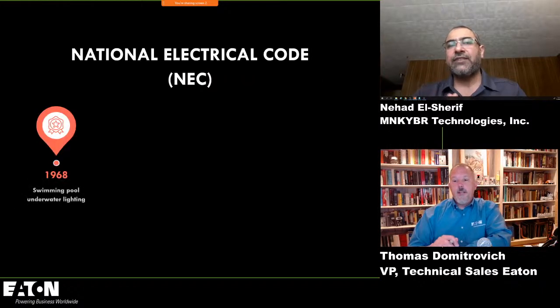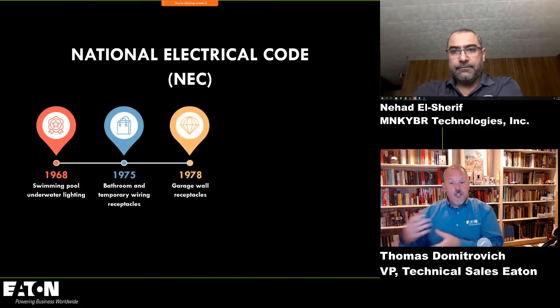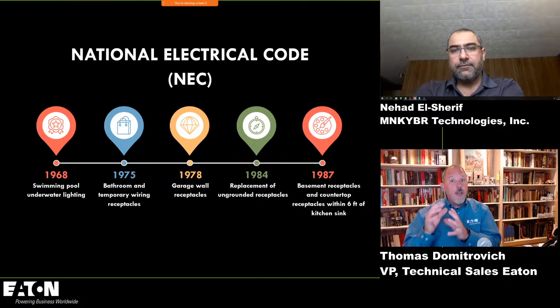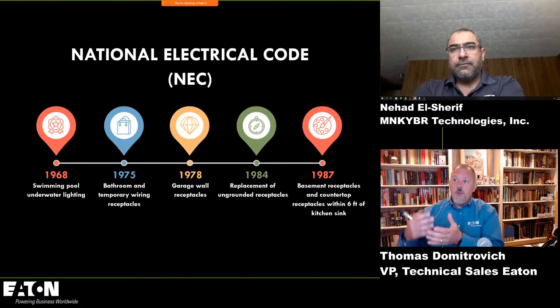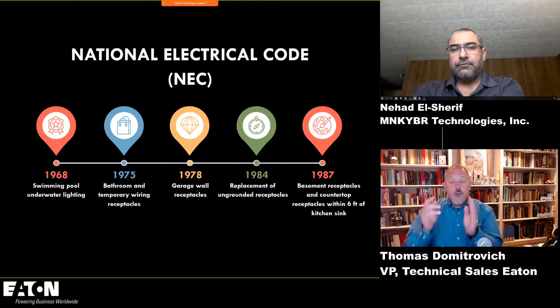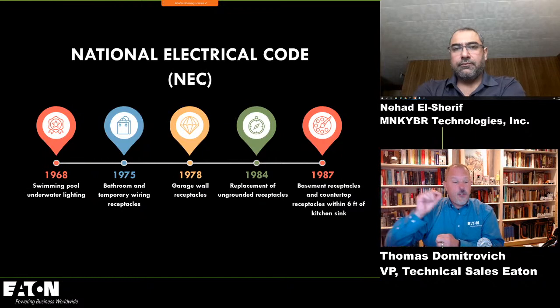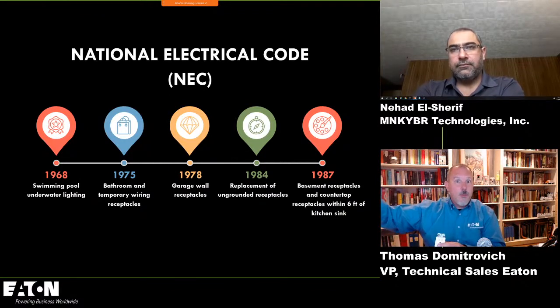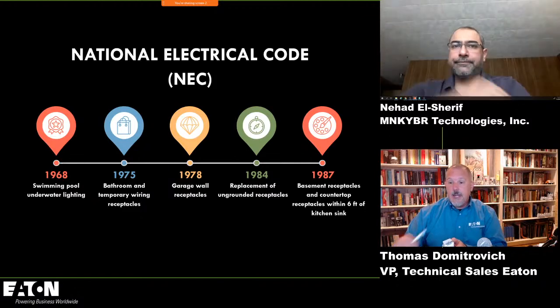Yep. And if we look at the National Electrical Code and how it's progressed over the years, GFCI protection first hit that book in 1968 for swimming pools and underwater lighting, for the obvious reasons. Probably they had people who were killed in swimming pools because of the shock and leakage currents and things of that nature. And it expanded to bathrooms and temporary wiring receptacles, then garages. In fact, in those early years, the equipment grounding conductor, 3-prong receptacles, took a journey in the NEC, where two-prong receptacles were permitted, and then they added that you had to have the equipment grounding conductor connected to certain areas within a residential home, and eventually you can't buy receptacles for a new installation that don't have the equipment grounding conductor prong in there.